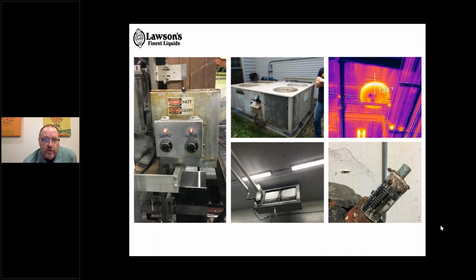Then things like that chiller unit, again at the warehouse, this is a low cost change. That thing was frozen solid as a block, so no air was moving through it. They were trying to cool a big warehouse refrigeration unit and it wasn't working, it wasn't doing anything, just glycol going in and coming out with nothing happening. So just going in and changing timers and putting in longer defrost cycles cleared that up and made it hugely more efficient.